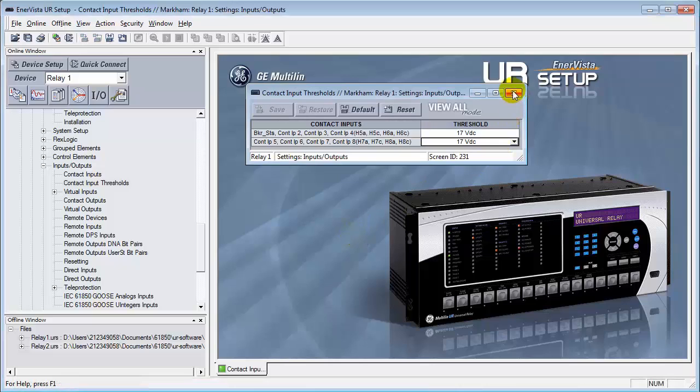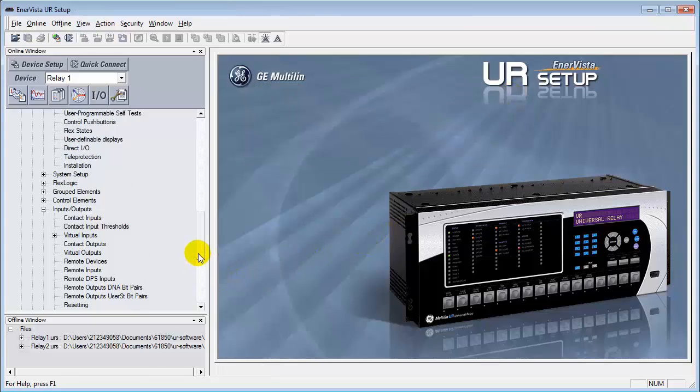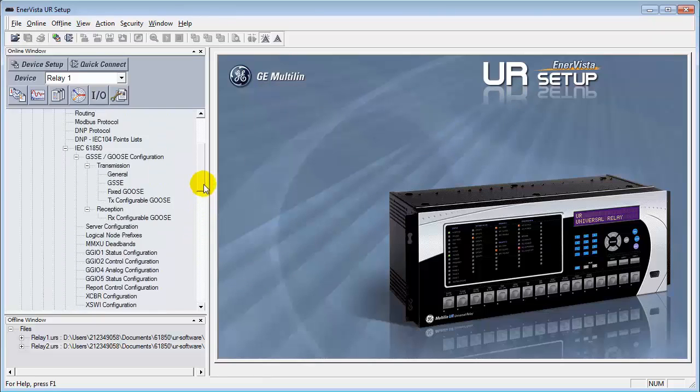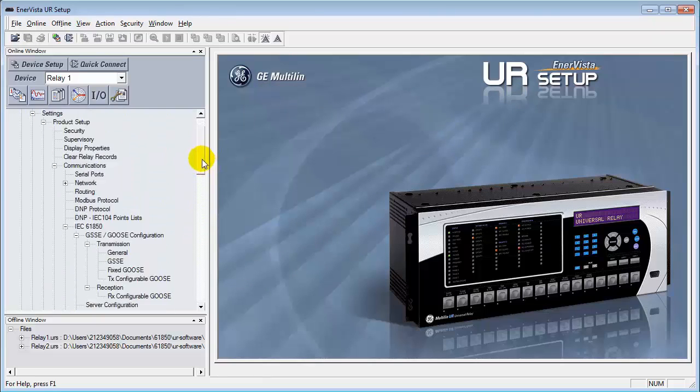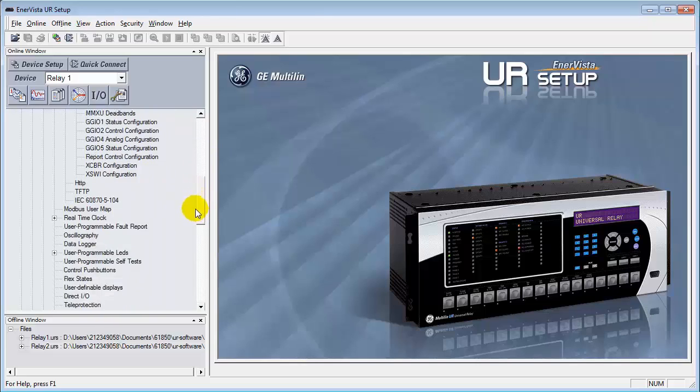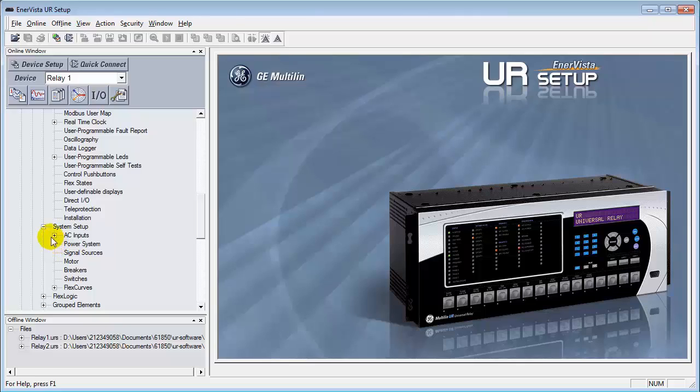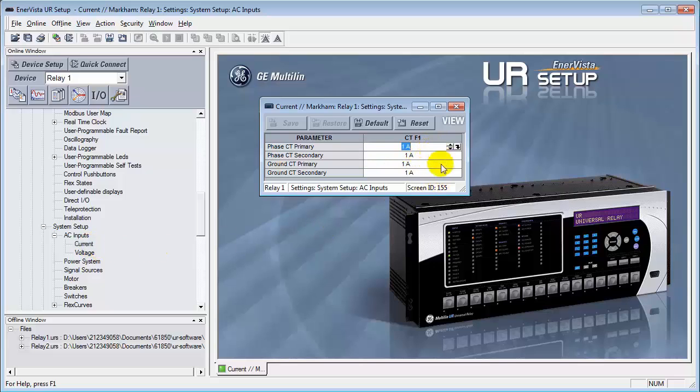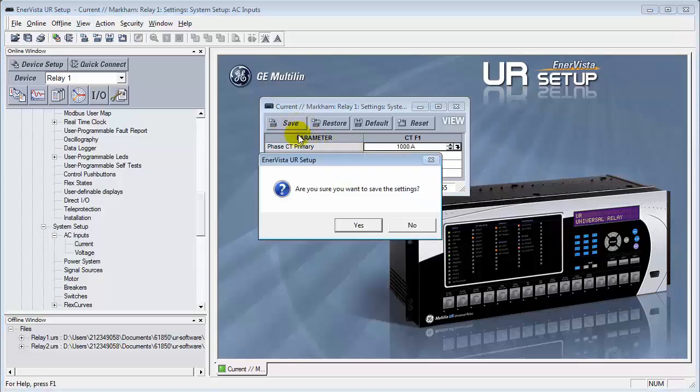The other thing that we need to configure as well is to verify that the metering portion is working as well, because we'll be sending analog signals. From the Setup program, System Setup, we'll go in here into the AC inputs. Let's set up a configuration for the currents. And we'll change the CT primary from the default of 1 amp to 1000 amps primary. Leave the CT secondary as 1. We'll save this.